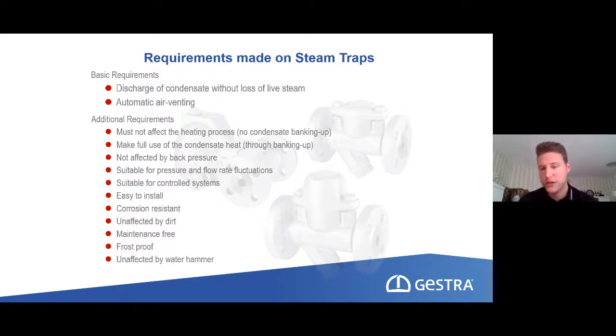And also this task will usually be done by a steam trap. So they're not just dividing steam and condensate, they also have to divide steam and air, which is sometimes a little more challenging because they both are in the gaseous state. So not this easy to differentiate here. So these are the things we have to do. And we also have the additional requirements, the things that are, let's say, nice to have. So it would be very nice if, in a heating process, we have no banking up of condensate.